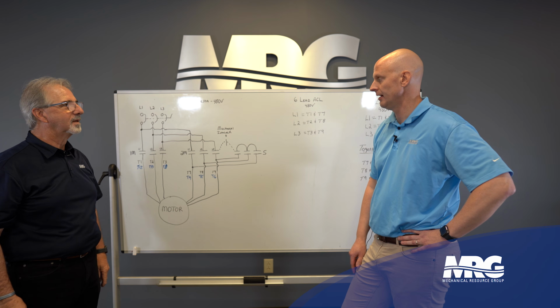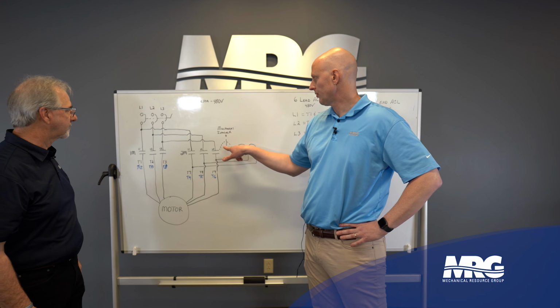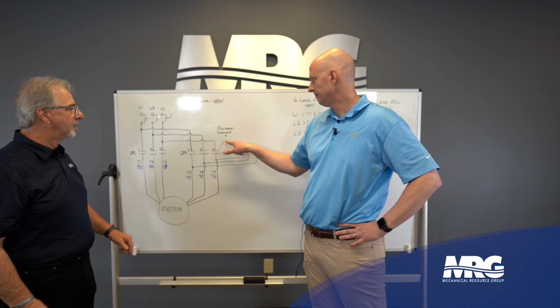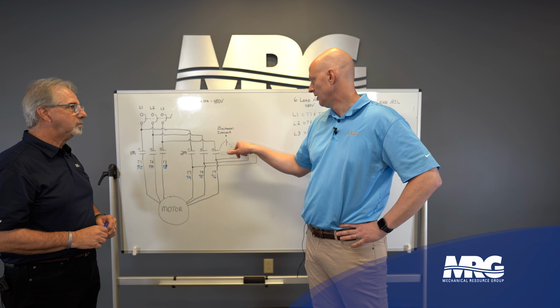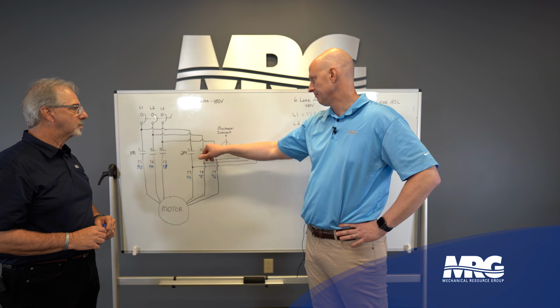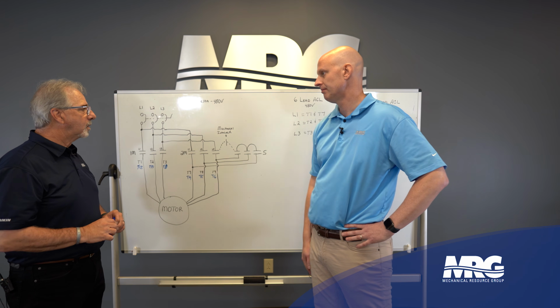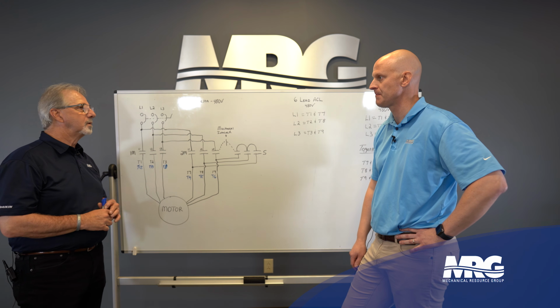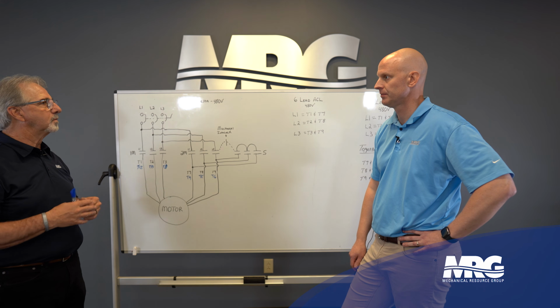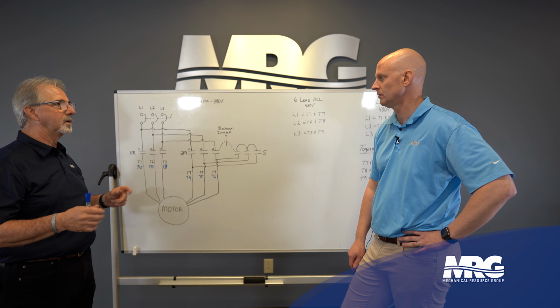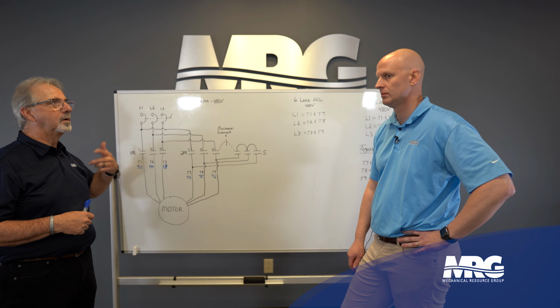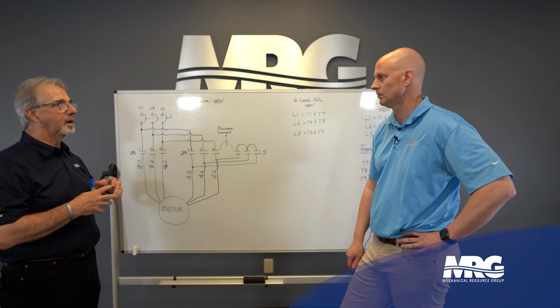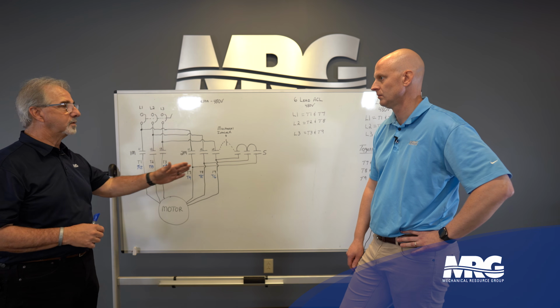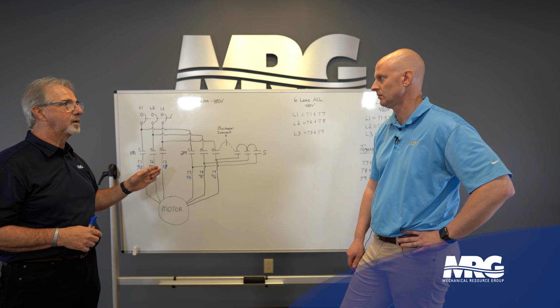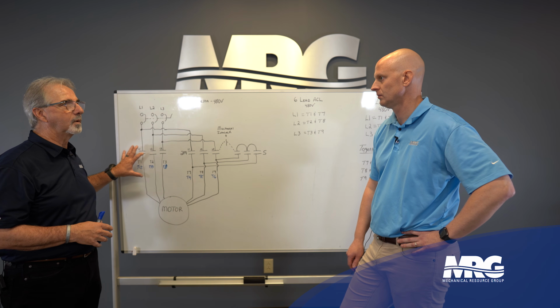Make sense? How critical is the timing between your Y-Delta releasing and then your 2M contacting? Well, it's very critical. What you don't want to do is have it too long, because remember, I'm not starting with the full winding. So if I start that motor and I start picking up load and I don't transition and bring the rest of the winding in, I'm going to overcurrent half that winding.